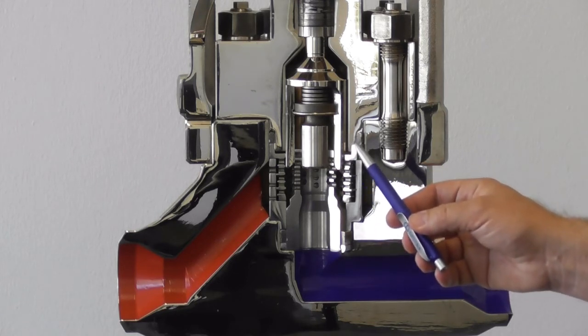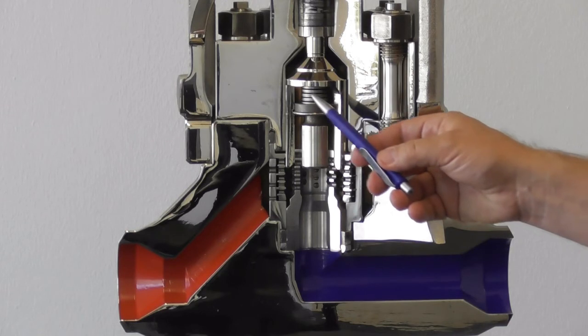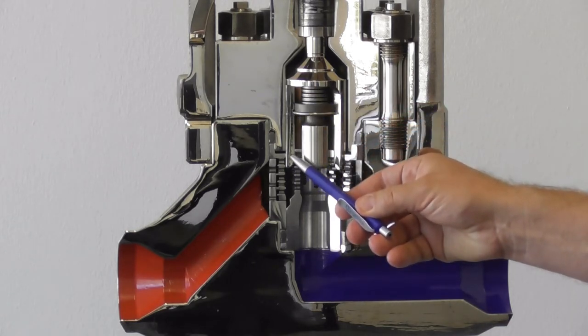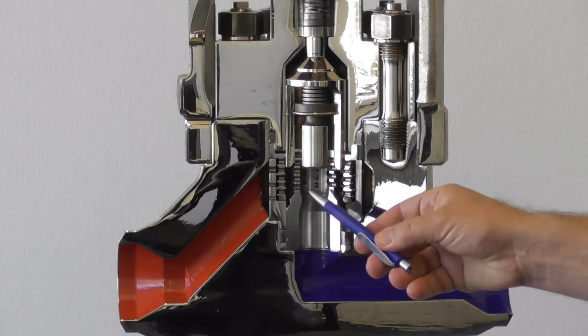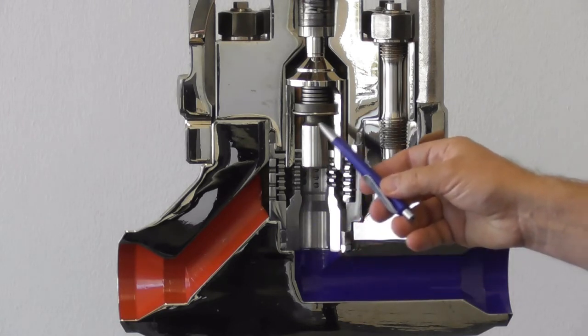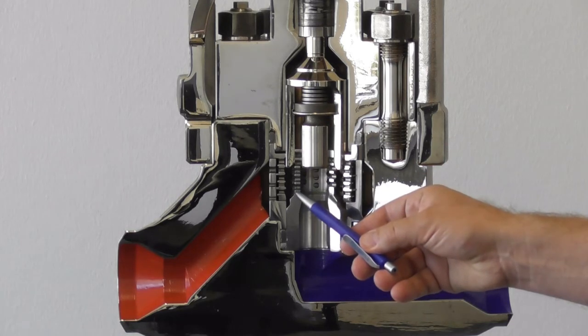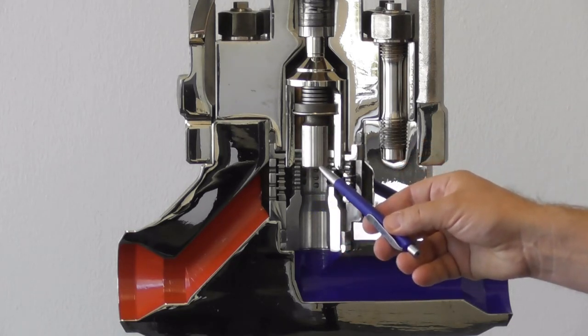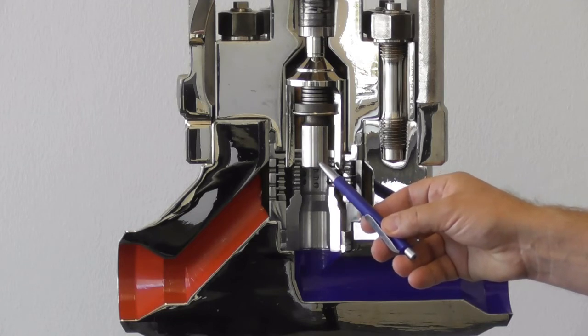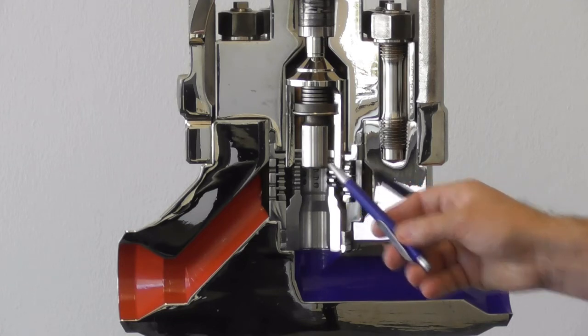Now how it works. We are going down with the main valve plug into the direction of the main seat. But before the main valve plug touches the seat, we are interrupting the flow with the secondary valve plug, with the cone, which I want to show now.